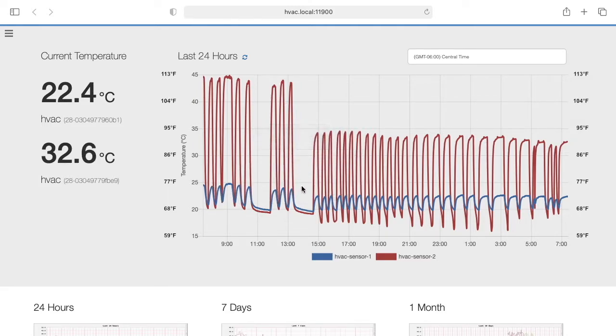On the regular furnace it's not quite as consistent, although I have seen it be consistent too. This is a variable furnace — it goes from 35% to 100% in 1% increments, so it can adjust its output pretty accurately. You can also see that on the heat pump the input side dips quite a bit lower. I measured this in Fahrenheit and it was around 68 to 70 on the blue here, and the output got up to about 76. My thermostat is set to 70.